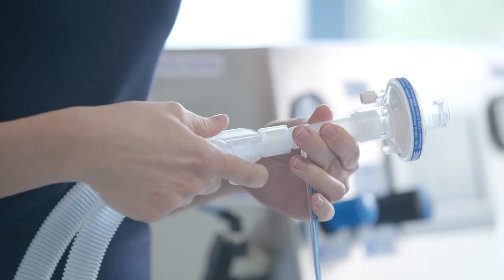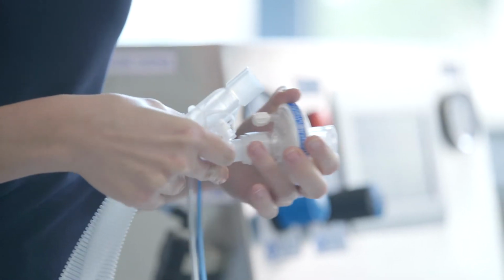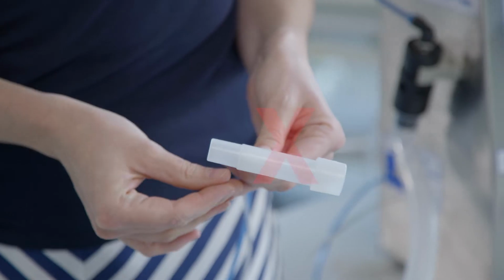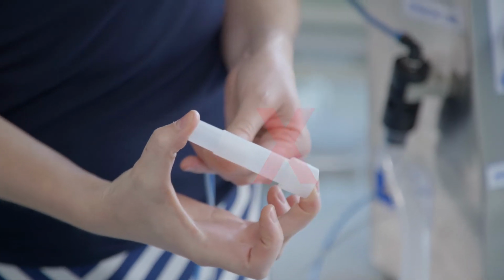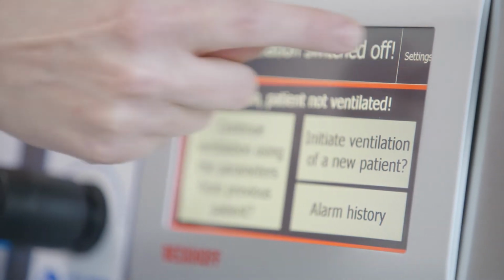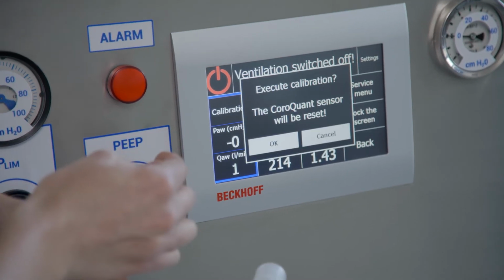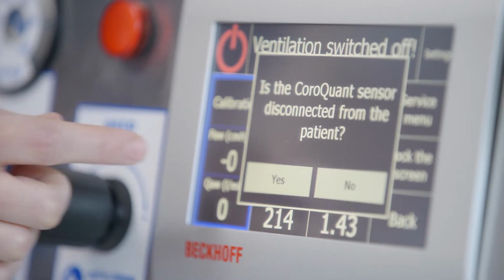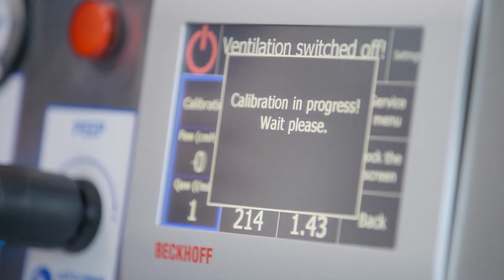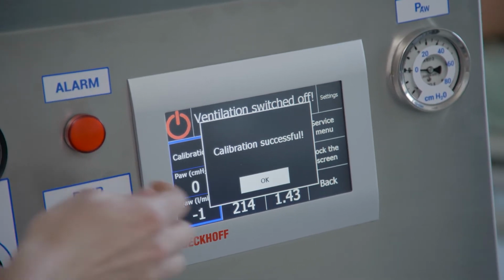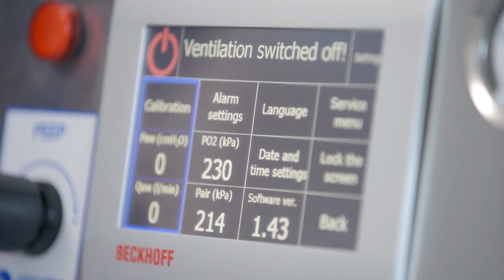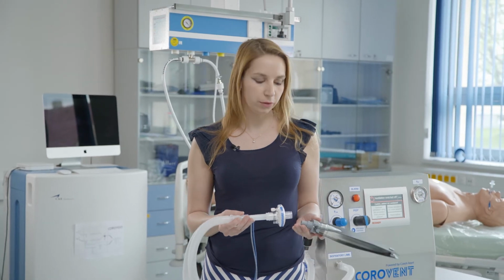Before we start ventilating the patient, we have to reset the flow and pressure CoroQuant sensor. We start disconnecting it from the breathing circuit and make sure the sensor is not exposed to any airflow and is not clogged. On the screen, select in Settings the calibration. The sensor will be reset. When it's finished, you return back to Settings. And now we can connect the breathing circuit to an artificial lung and start setting the ventilation parameters.